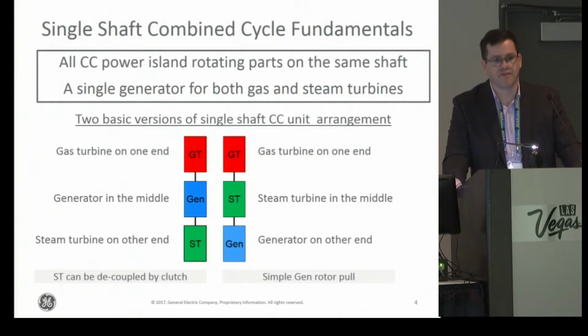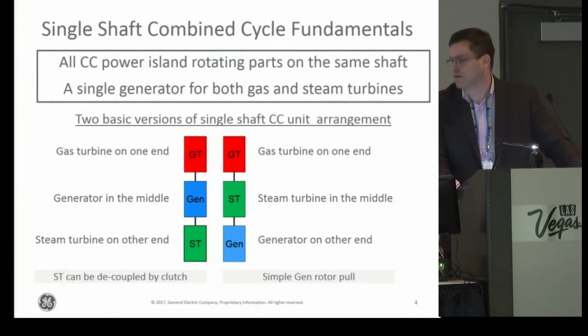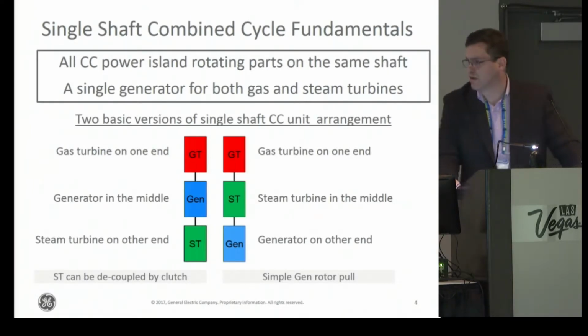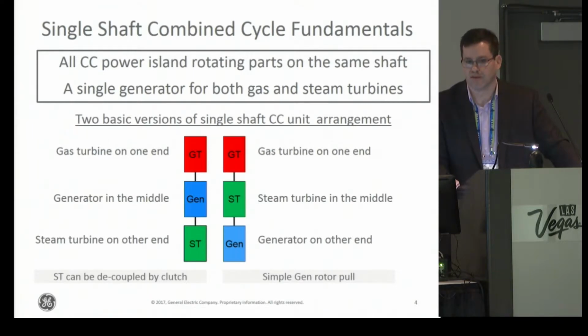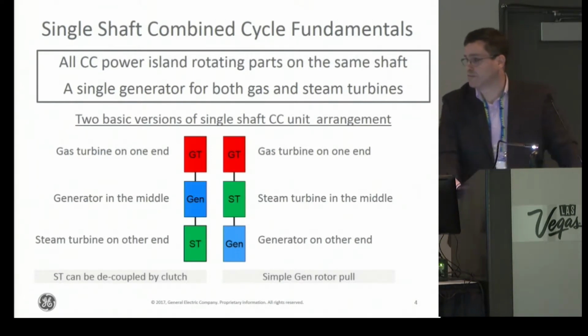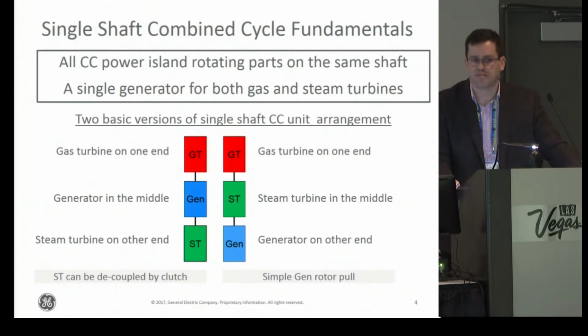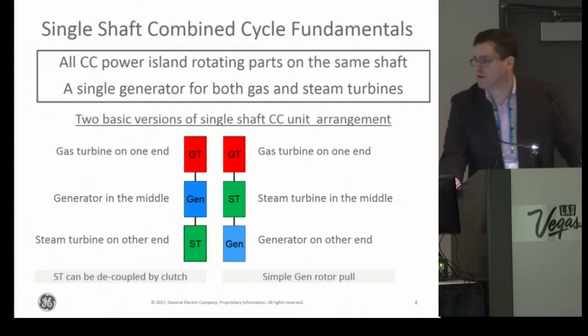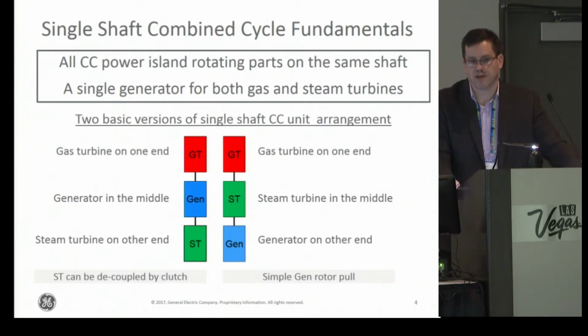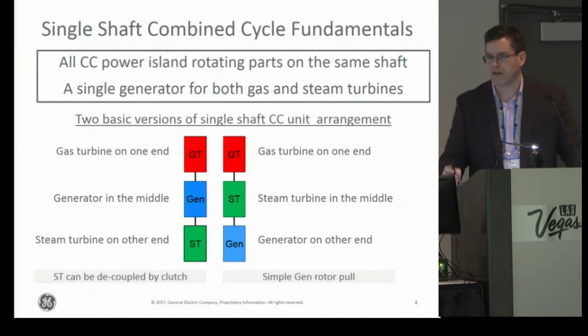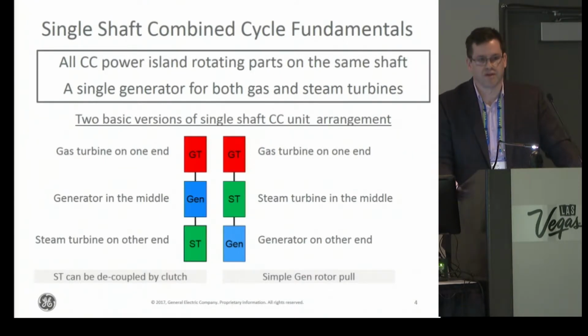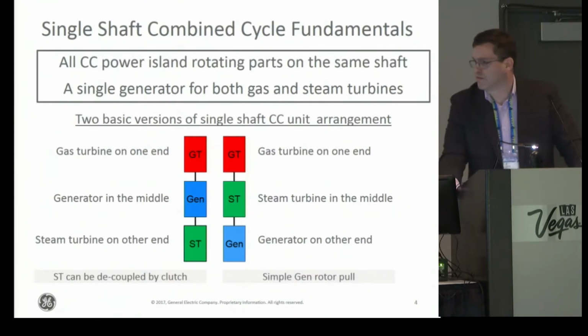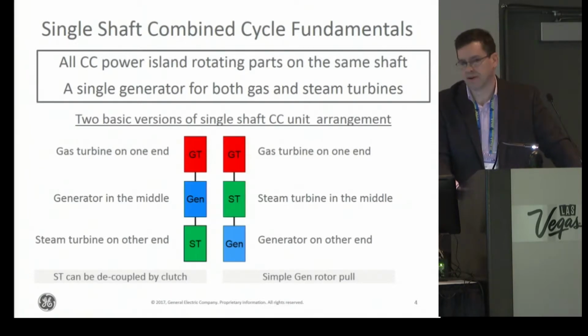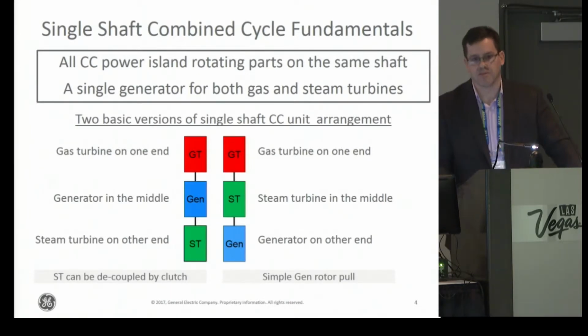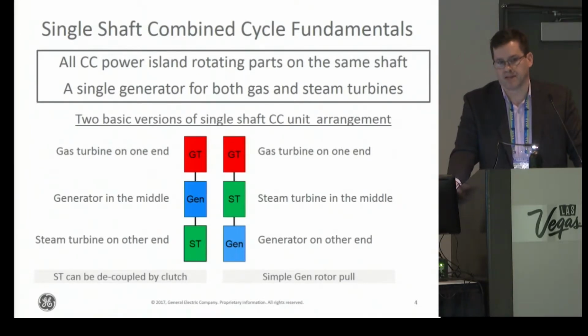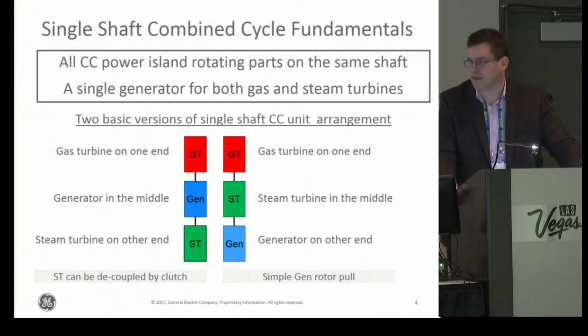There's two major configurations of single shaft combined cycle. One has the generator in the middle, shown on the left, the other having the steam turbine in the middle. There's pluses and minuses to each one. With the steam turbine in the middle, it's easy to pull the generator out of the unit for maintenance and inspection. With the generator in the middle, you have a bit better efficiency on your combined cycle for a number of reasons I'll get into later.